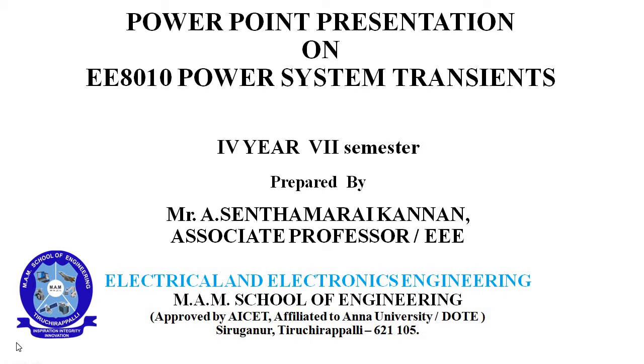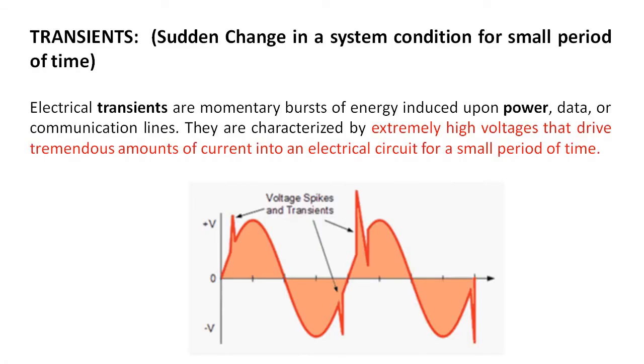Today we will discuss power transients. Transients, causes of transients, subdivision points. First point, internal causes. Second point, external causes. So define transients: a sudden change in a system condition for a small period of time. Electrical transients are momentary bursts of energy induced upon power, data, or communication lines. They are characterized by extremely high voltages that drive a tremendous amount of current into electrical circuits for a small period of time. In graphical representation, voltage is on the y-axis and time on the x-axis. The voltage spikes will be represented. That is called transients.